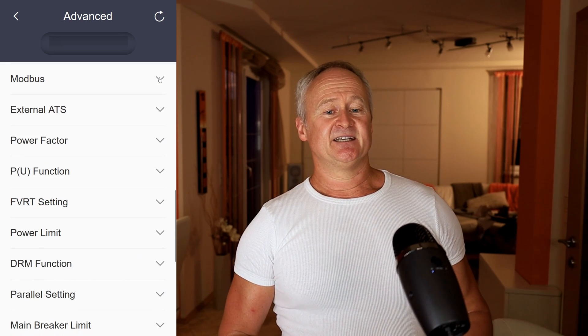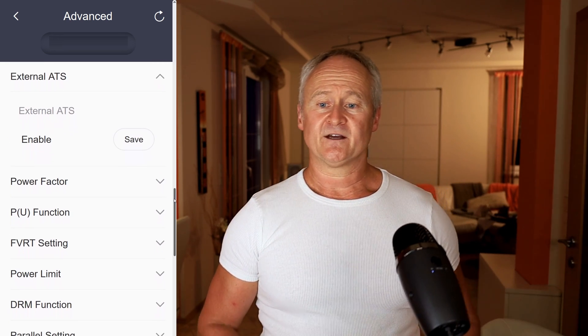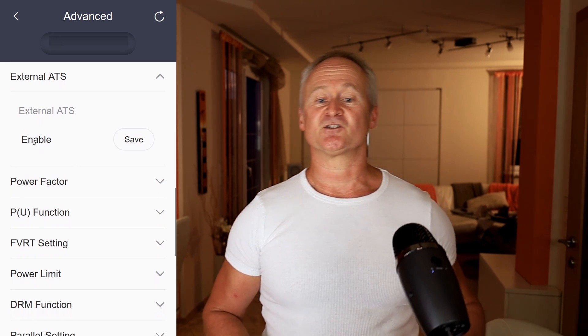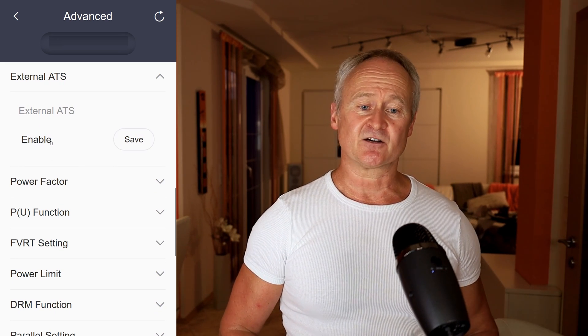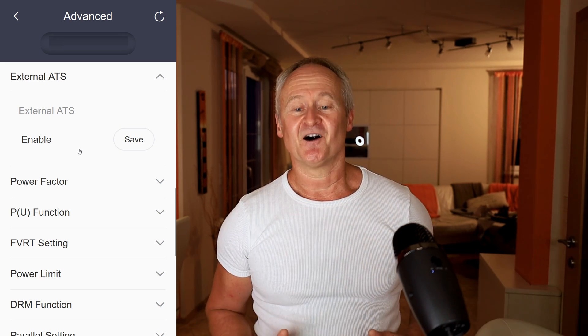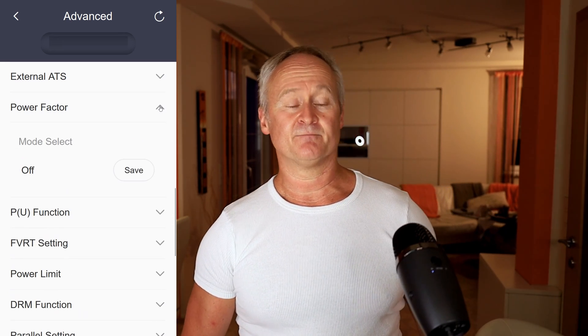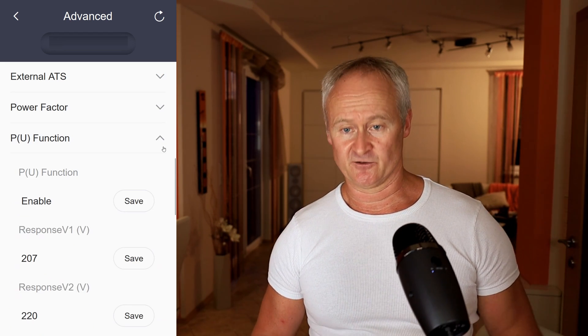External ATS — automatic transfer switch. Here you need to define whether you are using the internal grid separation of the inverter, the Solax X3 EPS box, or a manual switch to disconnect the public grid from your home network in case of a power outage. The Power Factor function and the next menu item P(U) function are related to the grid parameters. In most cases, you do not need to change the pre-configured parameters.